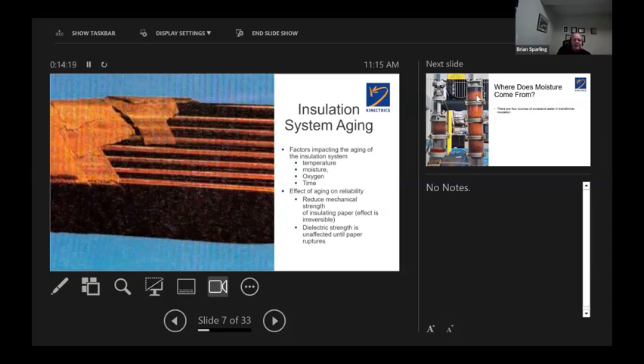What you're seeing here is a sample of a conductor taken from a rectifier transformer that failed under a small short circuit, but something it should have been able to sustain. And the company I was with at the time, we were doing sampling or testing of the oil in the lab, and we informed him that this thing's generating furans like crazy. It's a high temperature. You've got a high temperature problem inside this transformer somewhere. And basically they said, go away. None of my temperature alarms have gone off. So I think you're smoking grass.